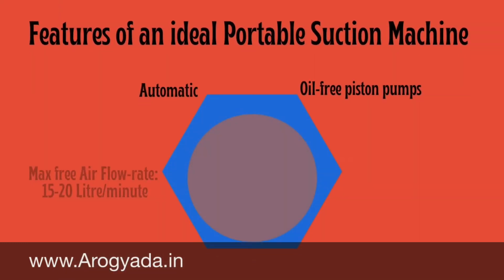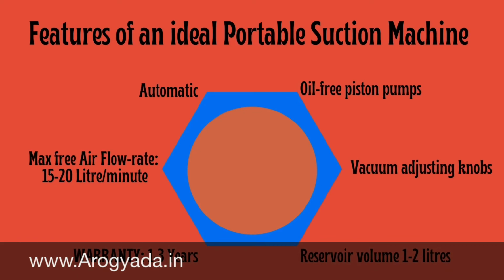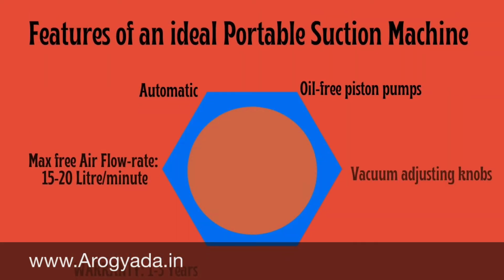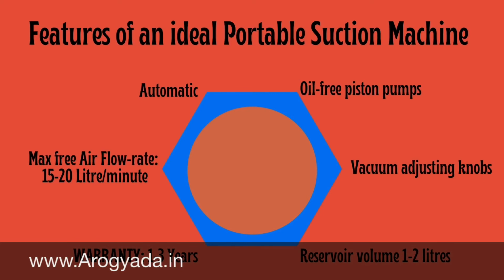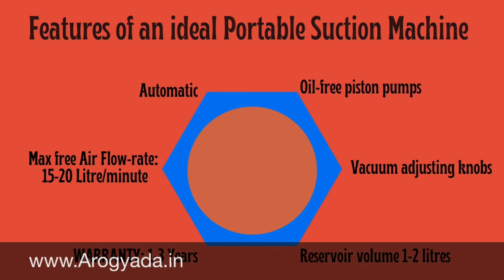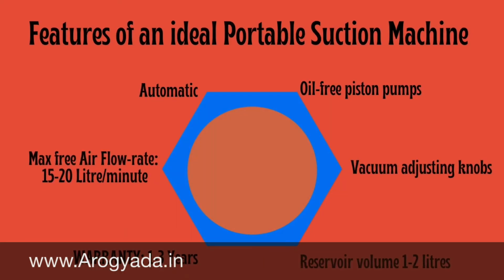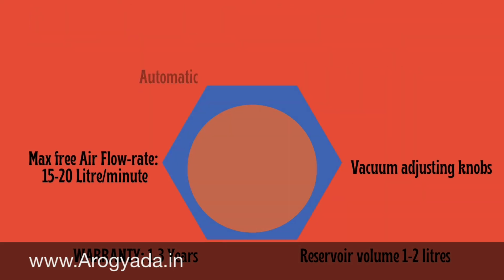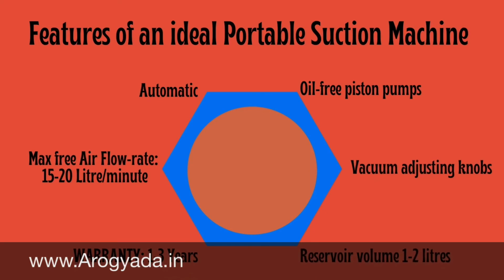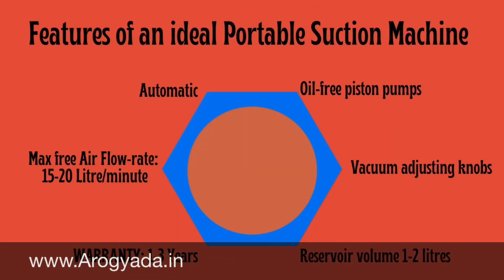What are the features of an ideal portable suction machine for home use? It should be automatic, lightweight and oil free, with piston pumps for zero maintenance. It should have easy to read vacuum gauges with precise vacuum adjustable knobs, and suction of at least 300 millimeters of mercury with a flow rate of 30 liters per minute. This is the maximum it should have. Anything between 150 to 200 is also fine, because ultimately the suction you will actually be using will not be more than 120 millimeters of mercury.